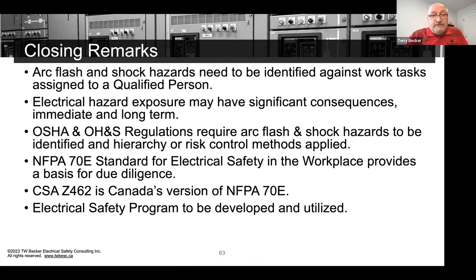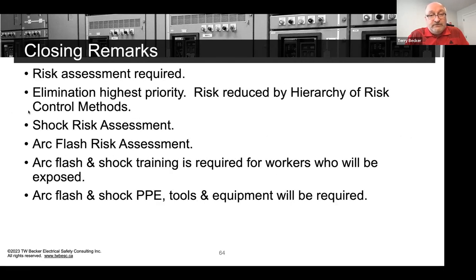All right, so we've adopted 70E in Canada as Z462. And I have to say, really, what's missing is employers need to get electrical safety programs developed. You need to control this. You need to control how these standards are interpreted and used and control how the training is applied. So that overarching risk assessment procedure, qualitative, work task based, again, I totally recommend it. I sponsor it. That's what you need to do to get control of this. Elimination is the highest priority. Apply those six hierarchy of risk control methods.